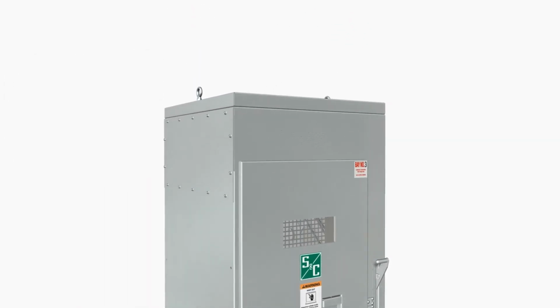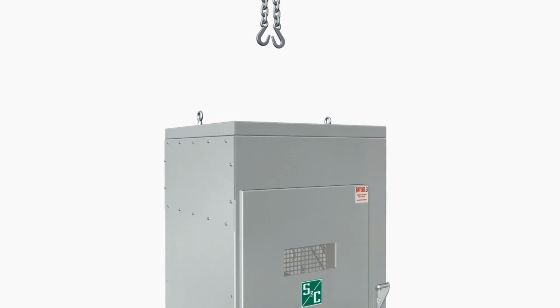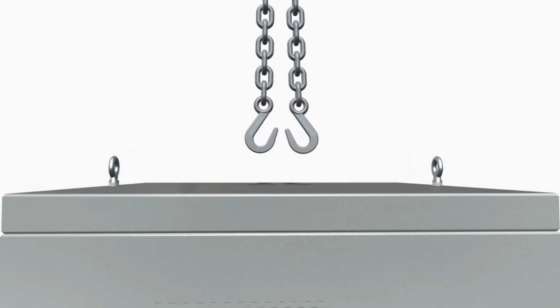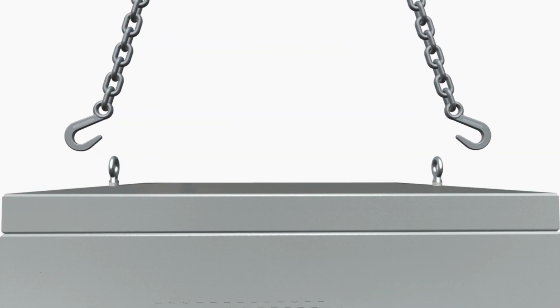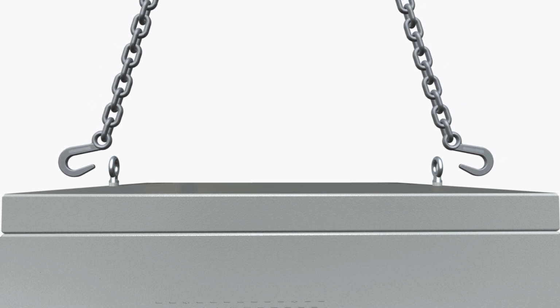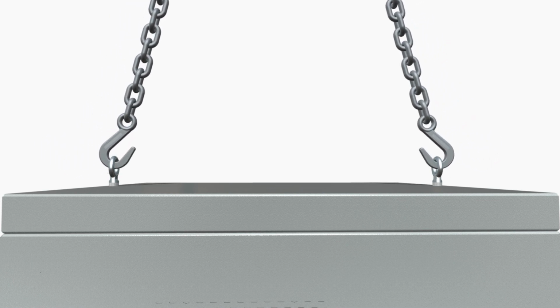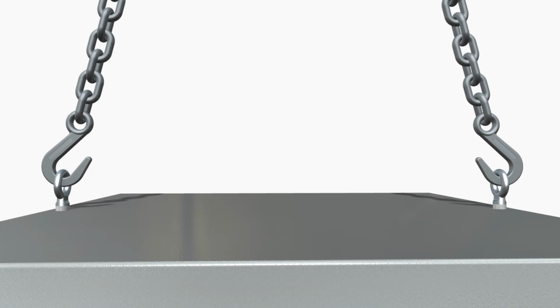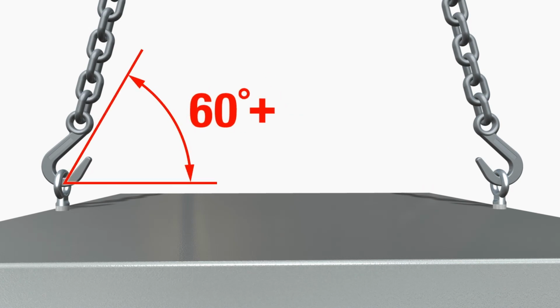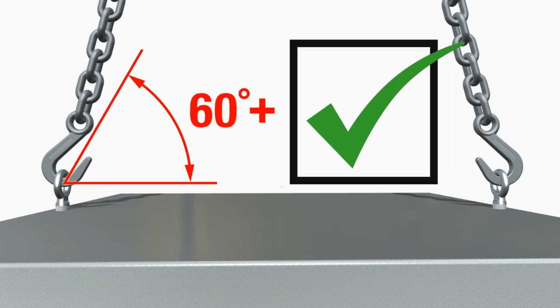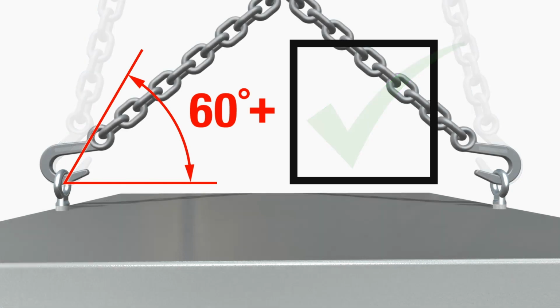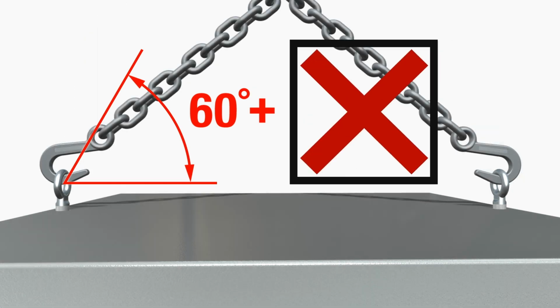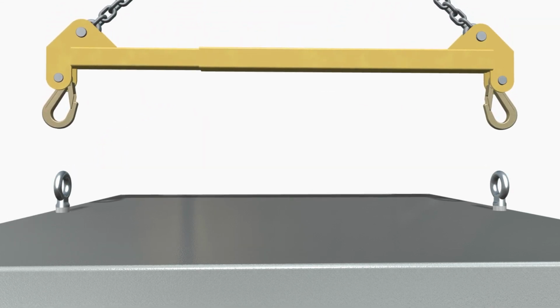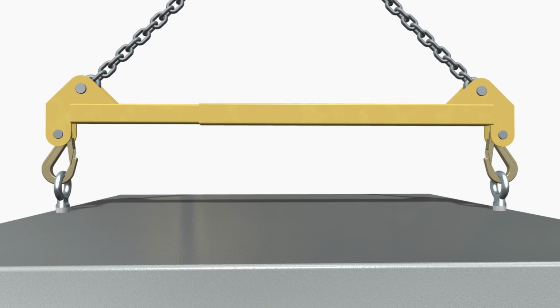When handling with an overhead hoist, follow these steps to avoid damaging the gear. Step 1. If possible, arrange hoist slings to distribute the lifting forces equally on all eye bolts. Step 2. Do not apply lifting force to any eye bolt at an angle less than 60 degrees from the horizontal. Step 3. If it is not possible to adhere to Step 2, use a certified spreader bar with hooks and lock clips.